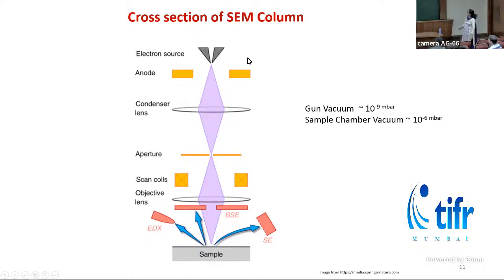But here is a cross section of the SEM column. So this is the electron gun, which can be tungsten or FEG, anything. It is accelerated downwards by these anodes. Then it has electromagnetic lenses. The first lens is the condenser lens. It focuses the beam into a fine spot. This lens also decides the current in the beam.